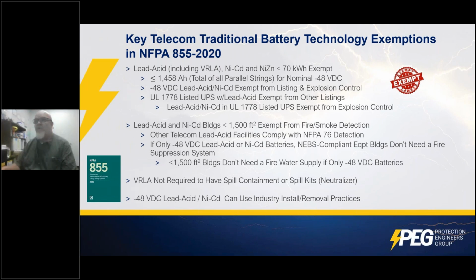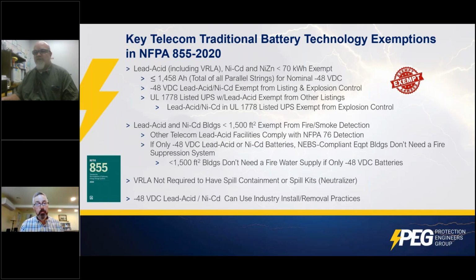All right, so here are some of the key telecom traditional battery technology exemptions in NFPA 855, realizing that traditional battery technologies really are not that big of a fire risk compared to lithium ion. So lead acid under 70 kilowatt hours was exempt. And 1458 amp hours in a nominal 48 volt DC telecom plant, that's where you're completely exempt. Once you get above that, you still have a lot of exemptions, but you're completely exempt if you're below that.